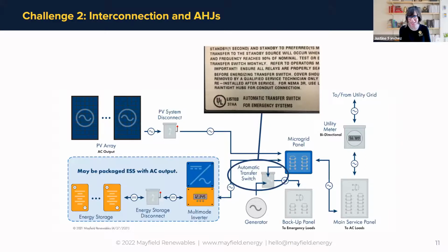Yeah, so this isn't really an interconnection question, but it definitely is an AHJ topic. What happened with our system is we went into a facility that had what's called an emergency panel. This panel is specifically put in place for serious health or safety issues, like exit lighting at a place of assembly where the power goes out and people might need to get out quickly and know where the exits are. Certain circuits within an emergency panel are legally required to be backed up by an alternate power source, historically a generator. There are different NEC articles, like Article 700, which is specific to emergency power systems, and very specific requirements for automatic transfer switching that has to be listed for emergency systems.